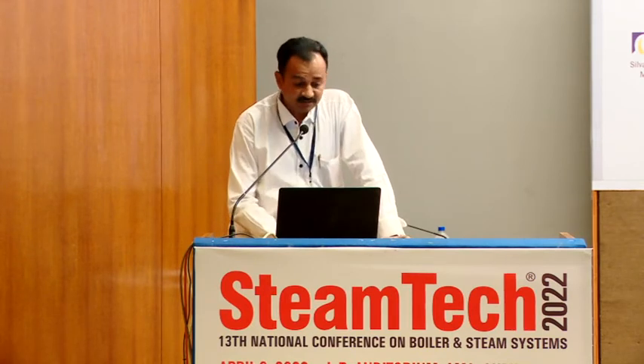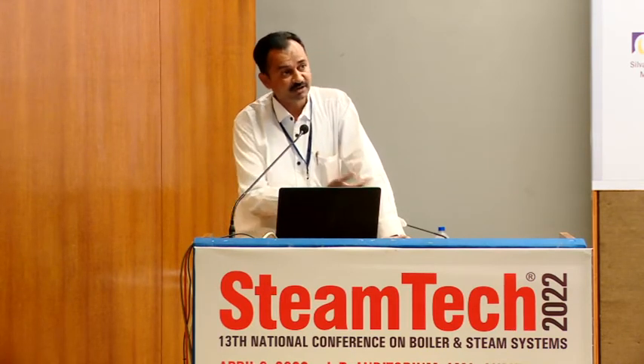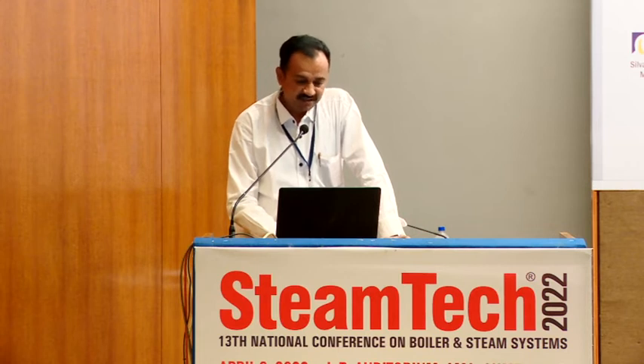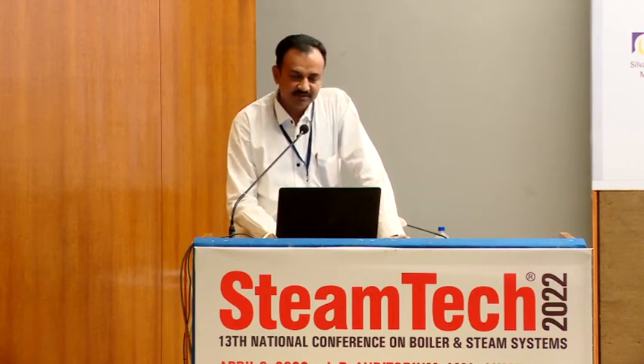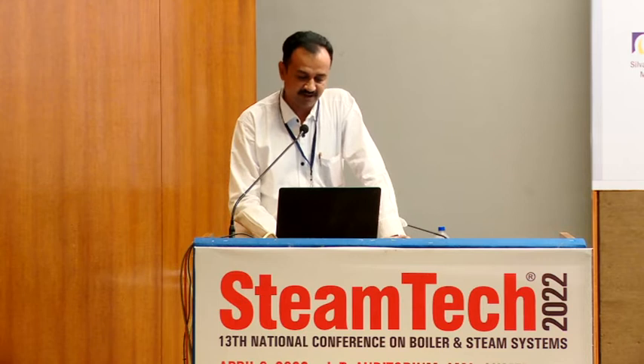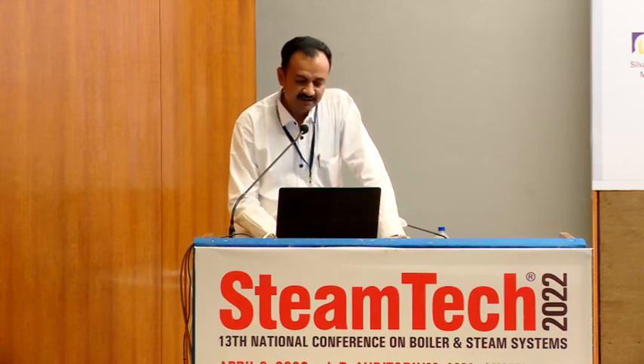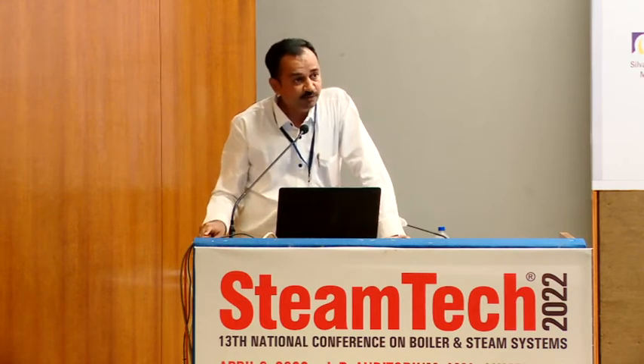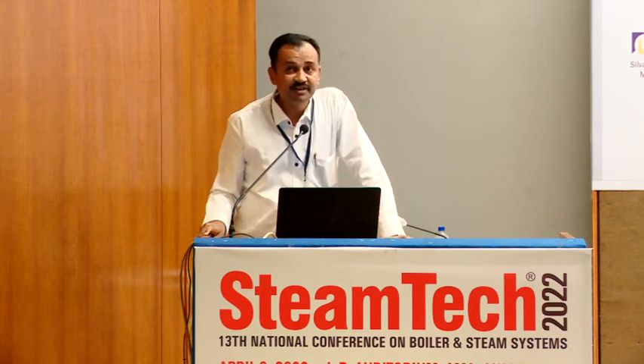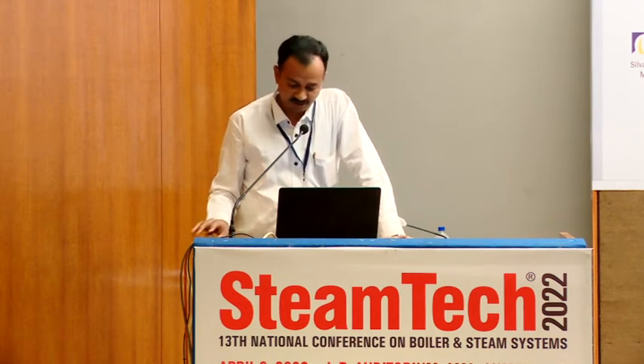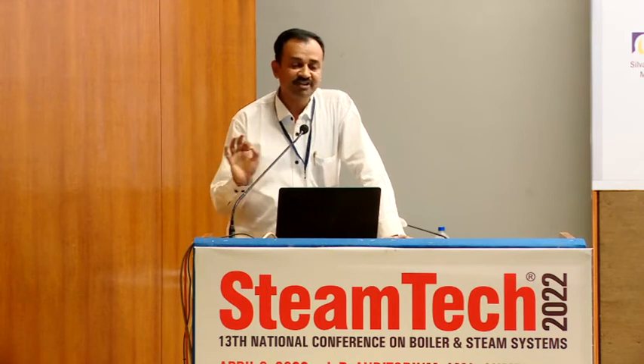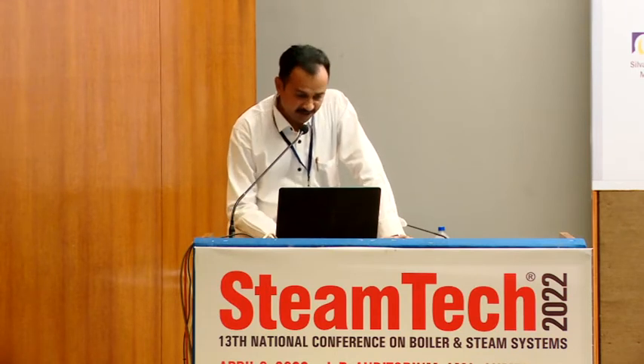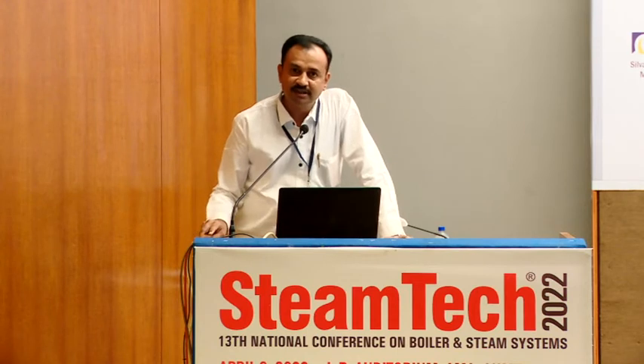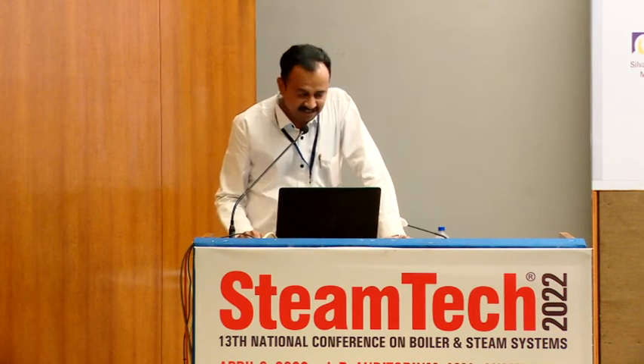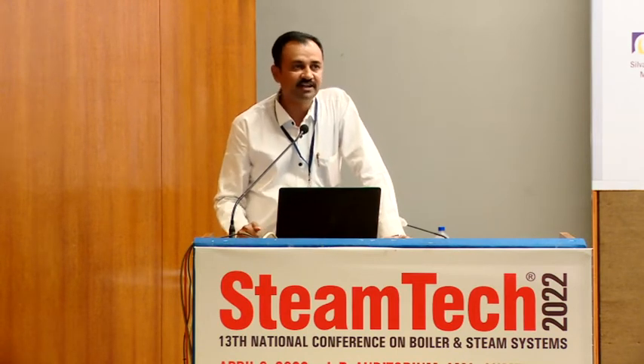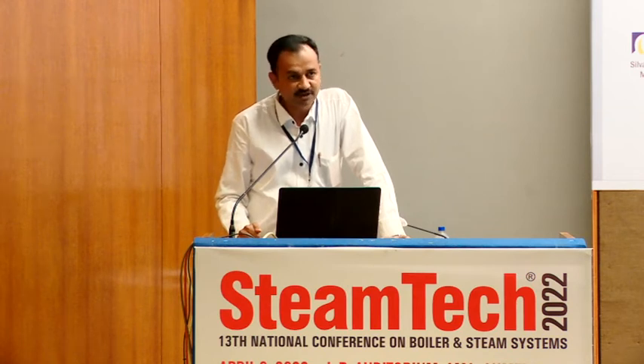And this is the analytics which we have pulled from the live connected sites of the boiler, where you can see that variations are always available. But the most important part is how we can synchronize the IDFD and feeder output with the operating condition of that boiler. That is possible first with the uptime. Here you can see I have taken reference of 16 customers, but our connected sites are almost 70 plus on the cloud right now.